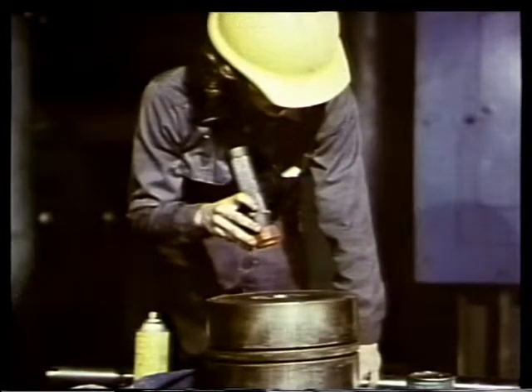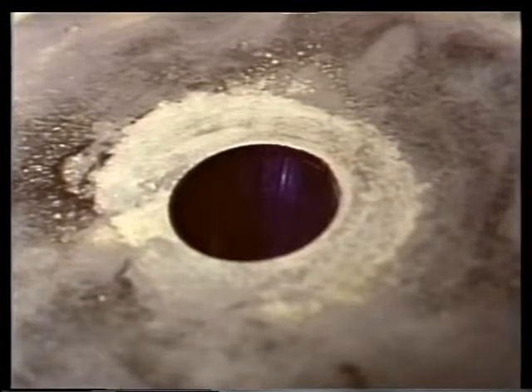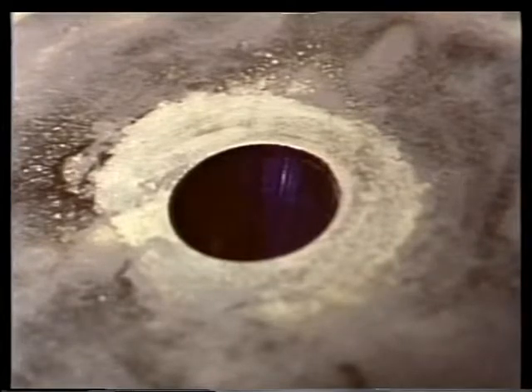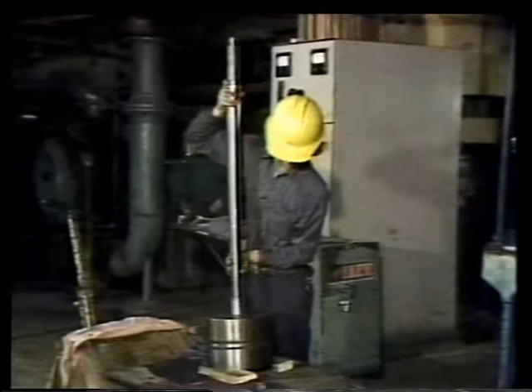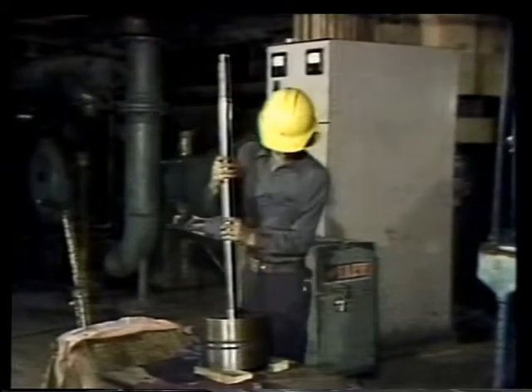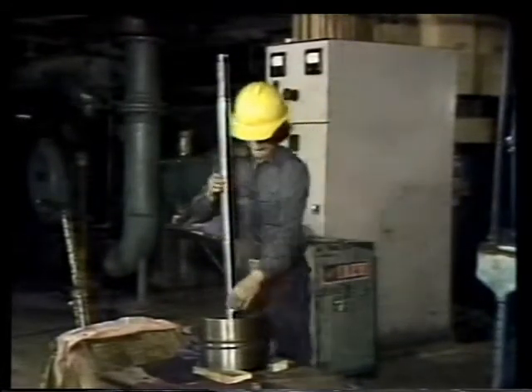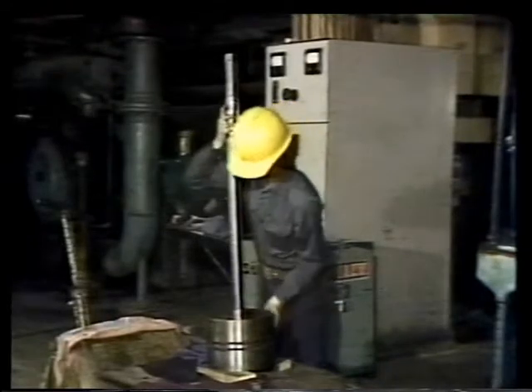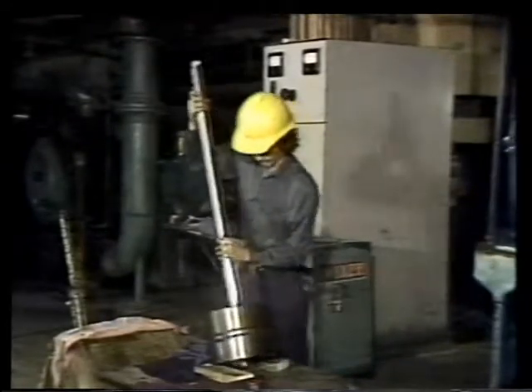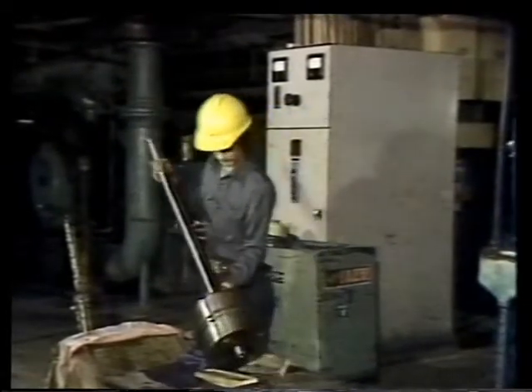Remove the piston rod and inspect the opening in the piston. If you can see a uniform ring of blue, the grinding in process is complete. Good contact has been made between the piston and the rod. If the ring pattern were not uniform, we'd need to repeat the process. Once the grinding in process is complete, the piston and piston rod can be reassembled. Insert the piston rod into the piston and lay the unit on its side.